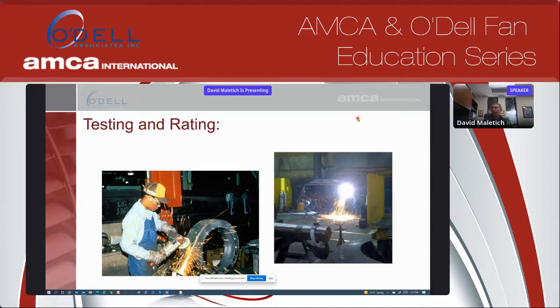So over the life of a fan, fans can be manufactured for 10 years, 15 years. What's to assure that during that lifespan of the manufacturing process the fan maintains its ability to perform as cataloged? After all, fans are fabricated, you have different people putting them together, you have different fixturing devices, and those can get worn out, they can go out of tolerance, etc.